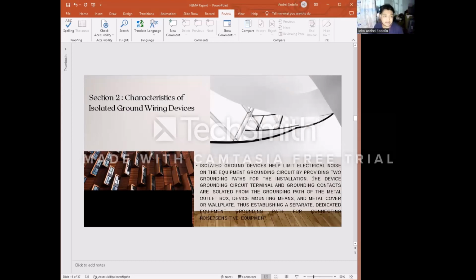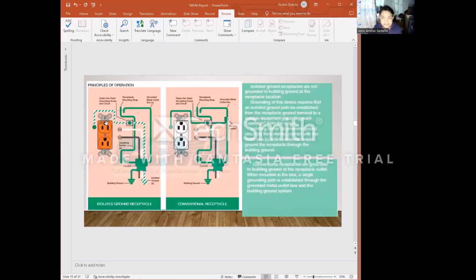Now, characteristics of isolated ground wiring devices. Isolated ground devices help limit electrical noise on the equipment grounding circuit by providing two grounding paths for the installation. The device grounding circuit terminal and grounding contacts are isolated from the grounding path of the metal outlet box, device mounting means, and metal cover or wall plate, thus establishing a separate dedicated equipment grounding path for connection to noise sensitive equipment. So this is the principle of the isolated ground receptacle.